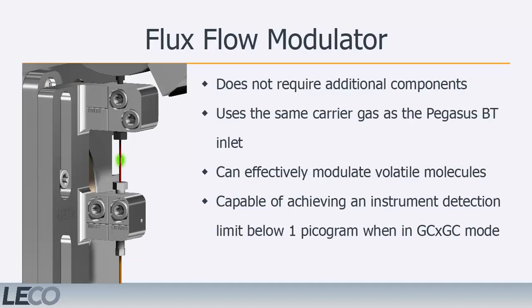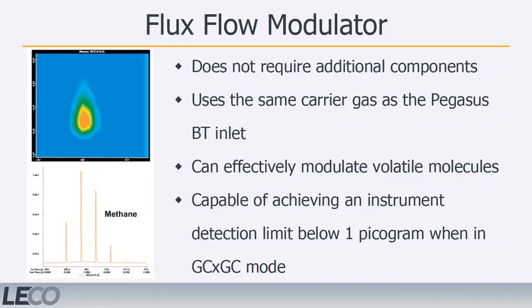LECO's version of the flow modulator is available in the Pegasus BT 4D, termed Flux. The Flux flow modulator does not require any additional components such as dewars, cryogens, or dry nitrogen. Instead, it uses the same carrier gas already used for the GC inlet. Because this method of modulation does not attempt to trap volatile compounds, the Flux modulator can effectively modulate small, volatile molecules. Here you can see data from a Flux system successfully modulating methane. Keep in mind the drawback of a flow modulator is higher detection limits when in two-dimensional mode than that of the thermally modulated units. However, the LECO Pegasus BT Flux is still capable of achieving an instrument detection limit below one picogram when in GC×GC mode.